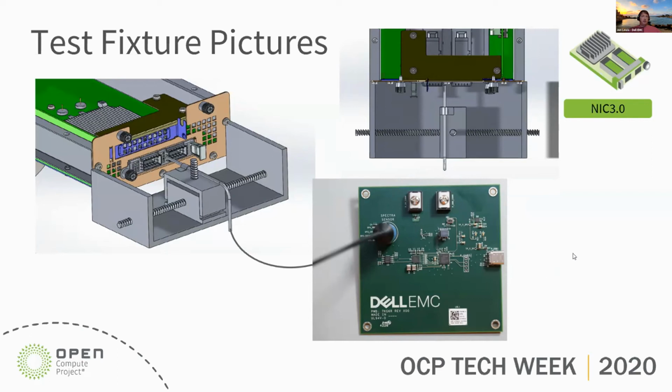The PWB, and what we're showing, thanks to the Intel ME team and Jonathan, is just a mock-up of a screw fixture that would allow for precise replication of testing. The test fixture that it's connected to is actually the thermal test fixture. That would hold the card rigidly, provide power and PCIe, so you would have a complete system there capable of adjusting the card as necessary.